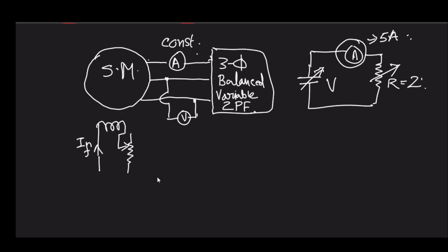So here, first you are varying the load and then you are varying the field current, and obviously after every variation step you need to wait a certain time so the machine reaches its new steady state condition. Do remember that the field winding is inductive, so even if you can vary the current, it takes certain time to build up. So you must allow for the settlement of transients, and then you can go on.